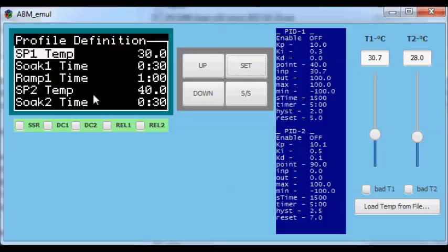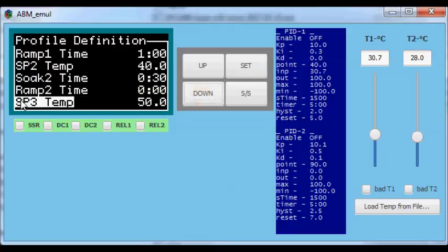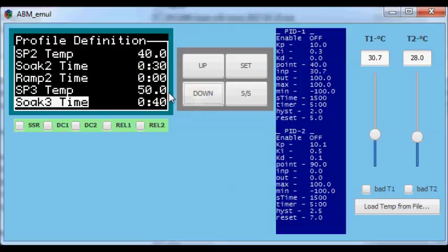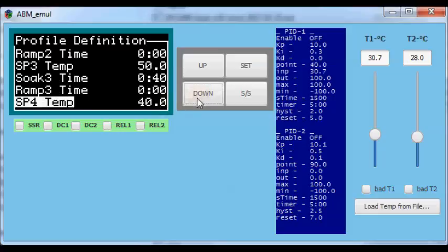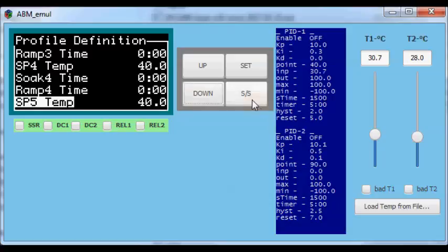Then the profile says: go to 40 degrees, with a ramp of one minute from 30 to 40. We keep 40 degrees for 30 seconds (soak time 2), and then we go to setpoint 3 at 50 degrees. In this case I put ramp time 2 equal to zero, which means the change from 40 to 50 is more or less instant — a step rather than a ramp. Then we keep 50 degrees for 40 seconds, and so on for all other steps. You can define up to eight points in your profiles.